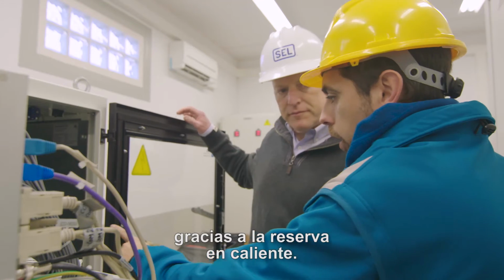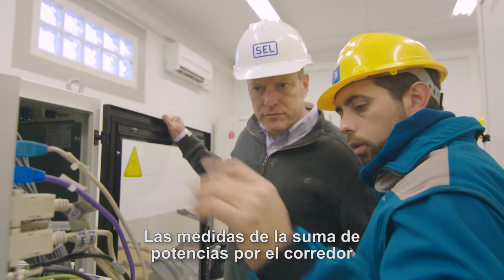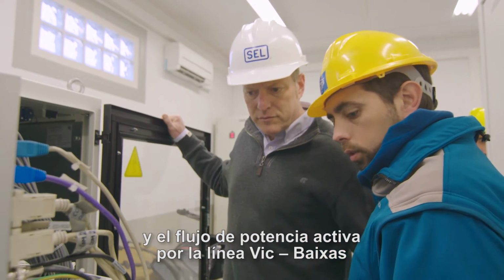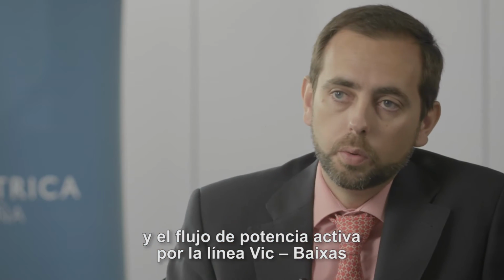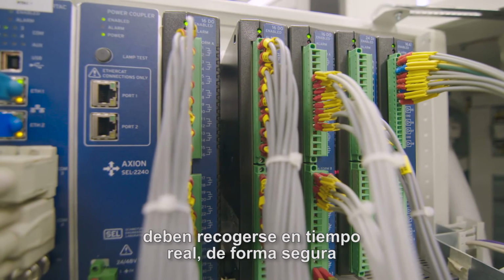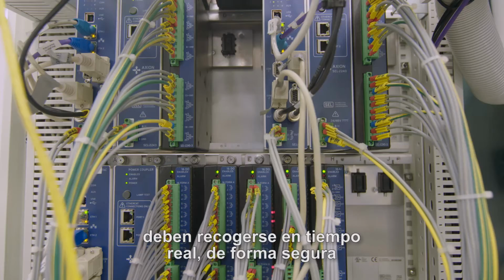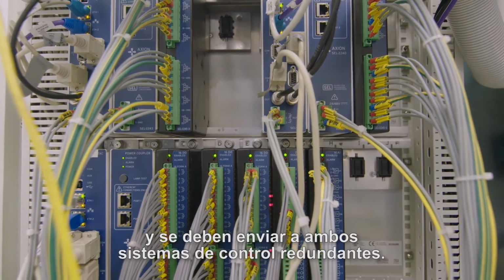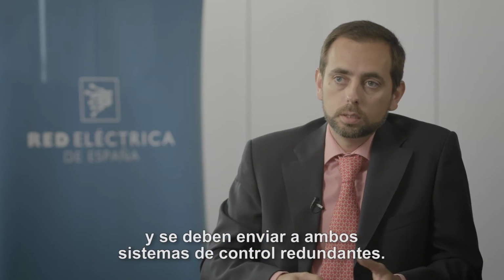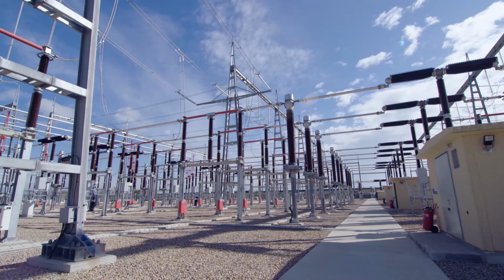The measurements of aggregate power and the active power flow through the most influential line should be collected in real time in a fail-safe manner and should be sent directly to both redundant converter control systems.